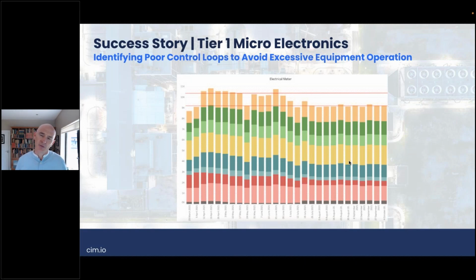The software then flagged that, and we raised what we call an action and assigned it to the site team to resolve, and they were able to resolve it in a matter of days. You can then see very much before versus after on that graph in terms of energy consumption, and that's at main meter level. So there's been a significant saving of, I think, around 78,000 kilowatt hours per year.